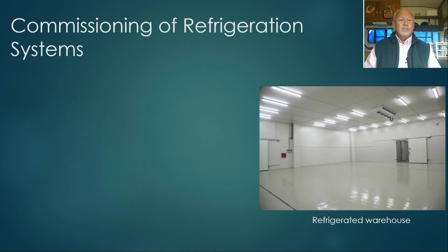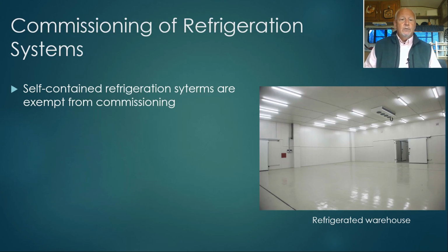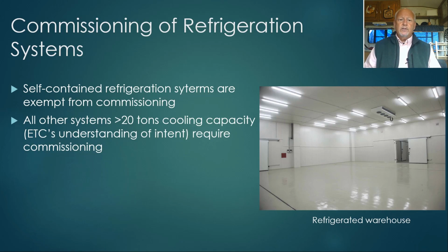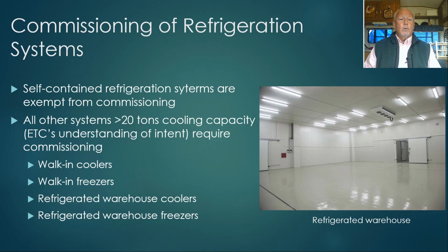Now, commissioning of refrigeration systems is required. Self-contained refrigeration systems are exempt from commissioning, so if it's a self-contained display case, that is exempt. All other systems greater than 20 tons cooling capacity, and again, the code is silent on this, but our understanding of intent is if there's more than 20 tons of refrigeration cooling capacity, then commissioning is required. And you would need to verify the proper operation of the systems. Now this, again, the scope would be walk-in coolers, walk-in freezers, refrigerated warehouse coolers, and refrigerated warehouse freezers.